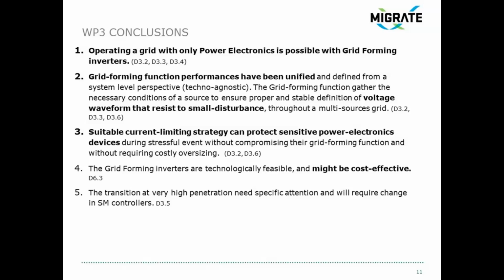So the choice between grid forming inverter and synchronous condenser is at least not based on cost. As I said, the transition to very high penetration might need specific attention for the remaining synchronous machines and a few updates of the parameters. So these were the conclusions that we had last year, because the MIGRATE project ended in 2019.